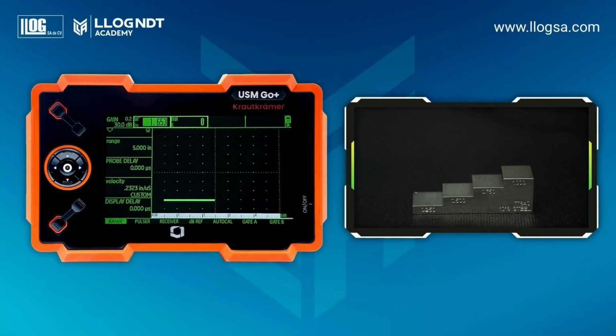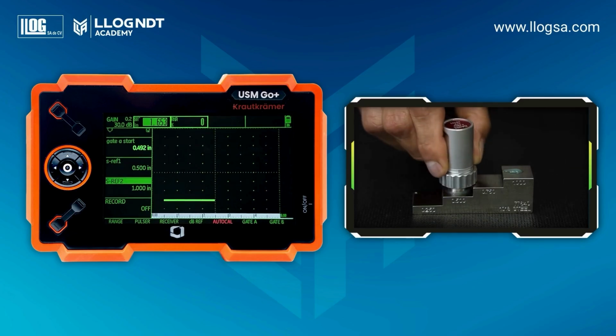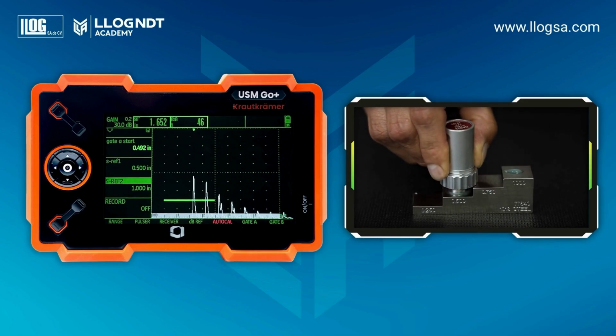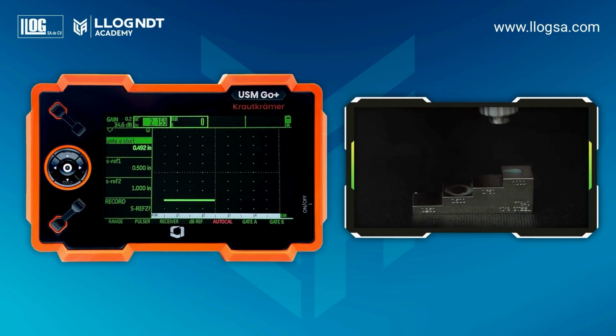Now we will perform the standardization using a dual probe and 2 known references. To begin, we access the auto-calibration menu. In reference 1, we enter the value of the smaller thickness to be used. In this example, 1/2 inch. In reference 2, we enter the value that corresponds to the larger thickness, 1 inch. We place the probe on the block at the 1/2 inch thickness. We adjust the gain until the first echo reaches an amplitude of 80%. In the record function, we press the right navigation key once to activate auto-calibration. To save the first reference, we press the right key again. Next, we place the probe on the 1 inch thickness and move the gate.